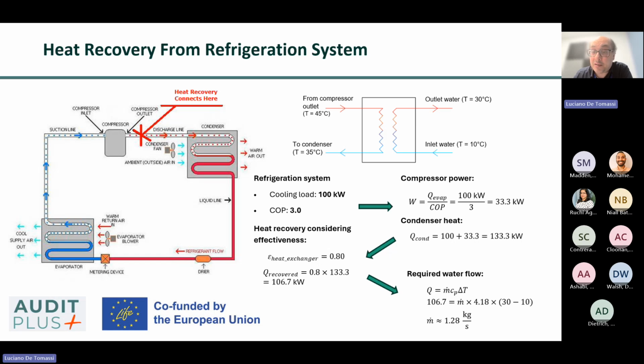In many retrofit applications, the heat recovery unit is installed in series with the existing condenser so that heat recovery is prioritized when there is a heating demand, while the standard condenser rejects any surplus heat when recovery is not required. On the refrigerant side, the hot, high-pressure refrigerant leaving the compressor passes through the heat exchanger before or instead of entering a conventional air-cooled or evaporative condenser. On the secondary side, a water loop is circulated through the heat exchanger, absorbing heat from the refrigerant and transferring it to a usable hot water circuit.